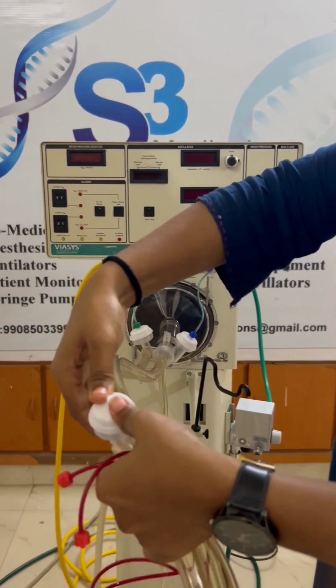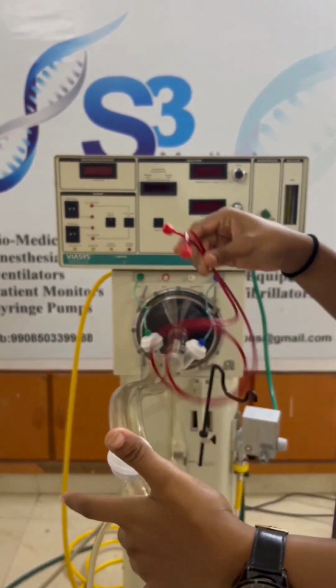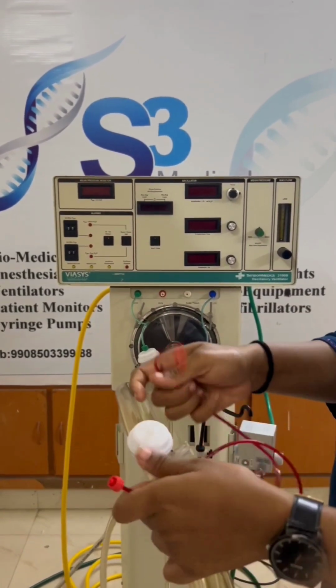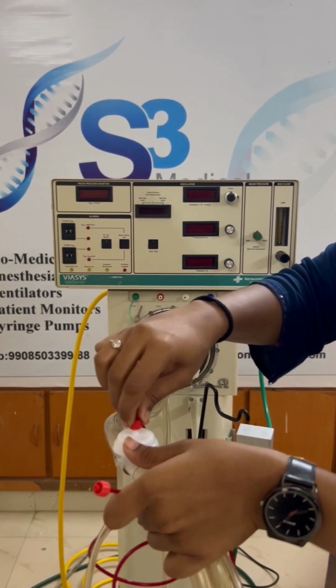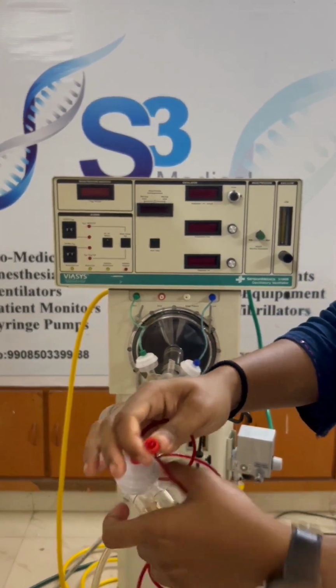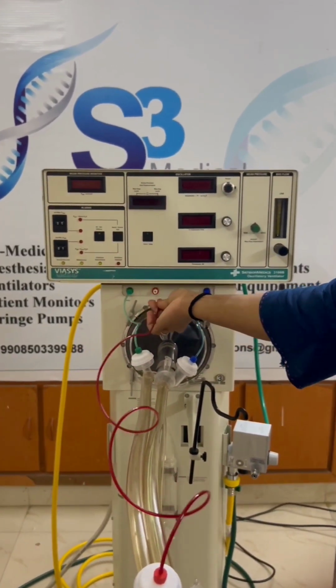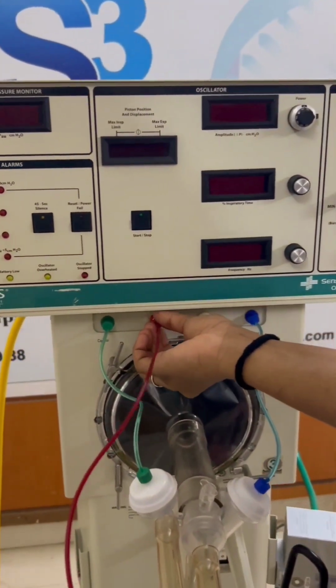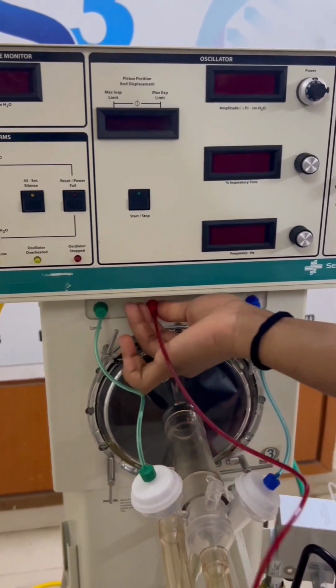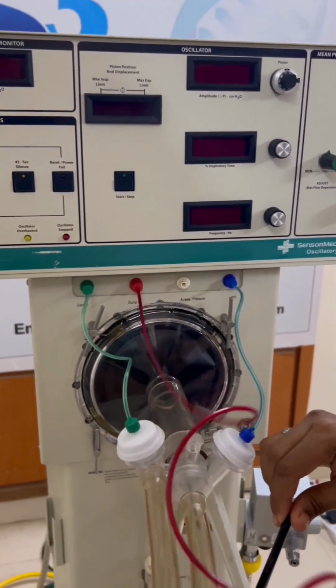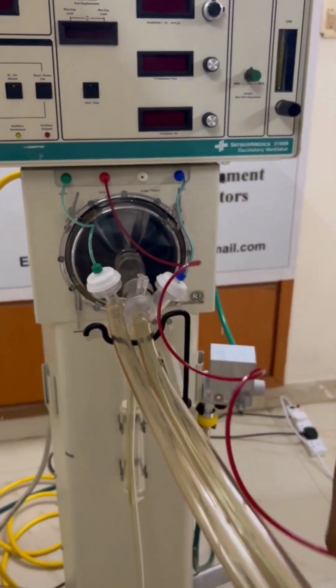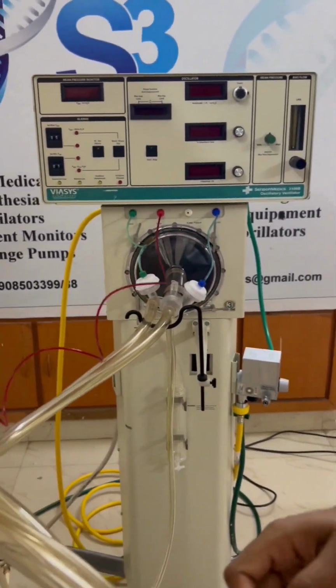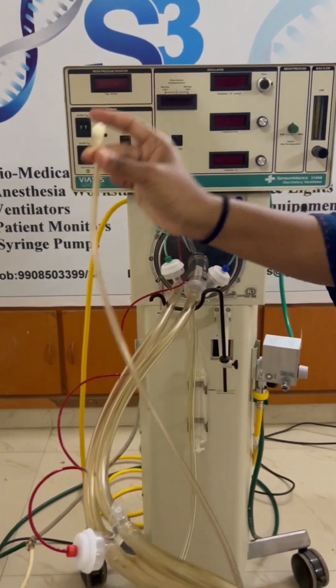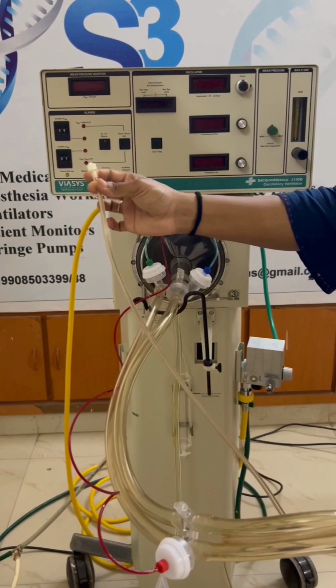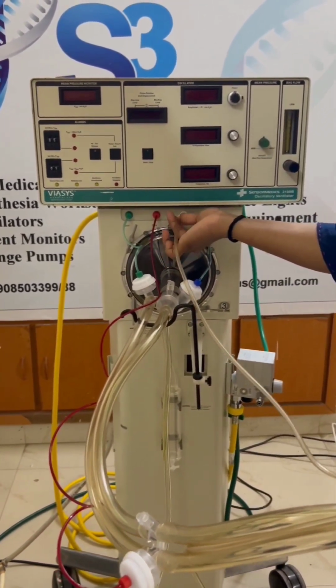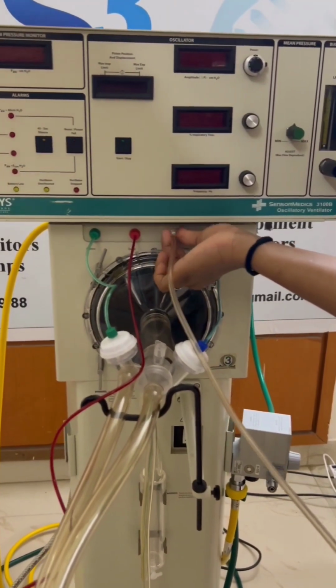The cap diaphragm set we need to connect to the circuit. And this red color is for the dump control. So we need to connect to the circuit on the cap, then to the ventilator. Then this should be connected according to the color coding on the ventilator. Fix it properly. After fixing this on the circuit, you can see the pressure amplitude line, it should be connected to the white area. It will connect to the ventilator. Fix it properly according to their color codings.